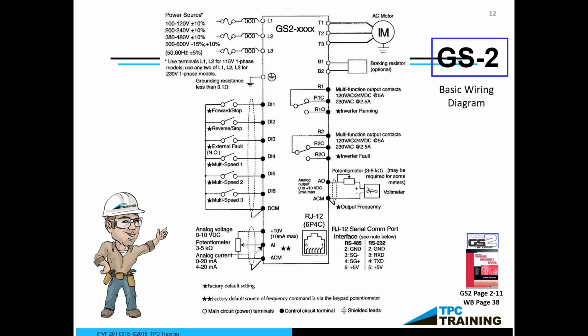And there again, have that communication port. It might be an RJ12 jack or a 232, and you're going to find the software is very easily and readily available for the majority of your systems. Sometimes it's free, sometimes it's not free, sometimes you have the cables, sometimes you have to purchase the cables. Nonetheless, whatever manufacturer you have, the software and the cables are going to be unique to that system.